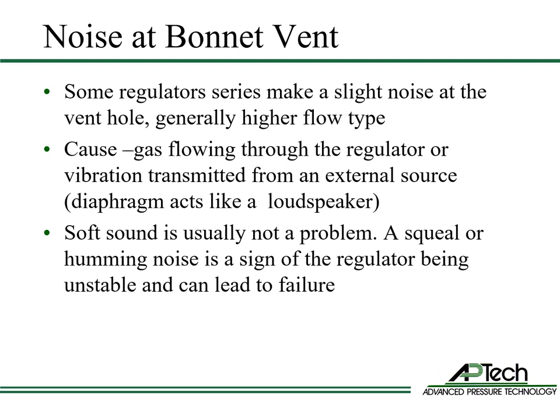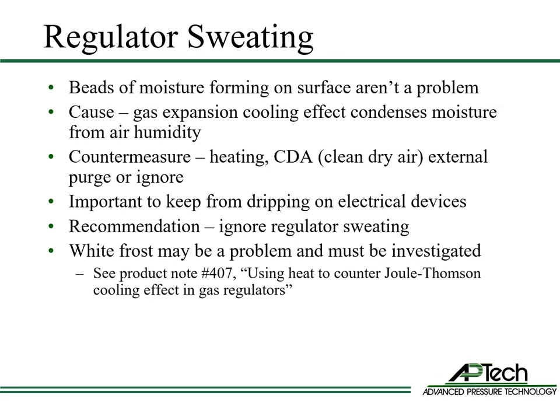A soft sound is usually not a problem. A squeal or humming noise is a sign of the regulator being unstable and can lead to failure. Regulator sweating is when beads of moisture form on the regulator surface and are not a problem. The cause is the gas expansion cooling effect, condensing moisture on the regulator surface from humidity in the air.